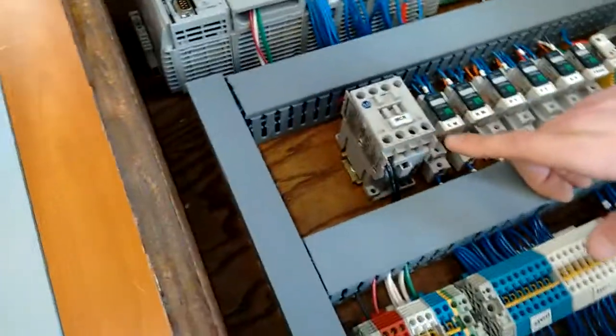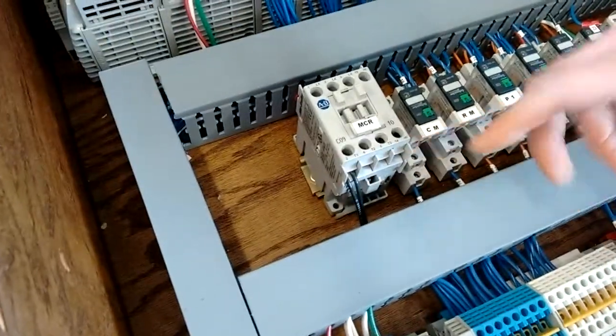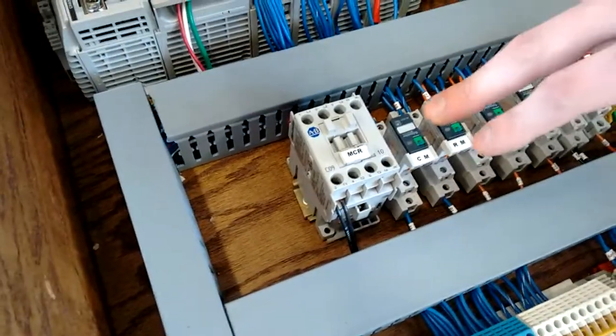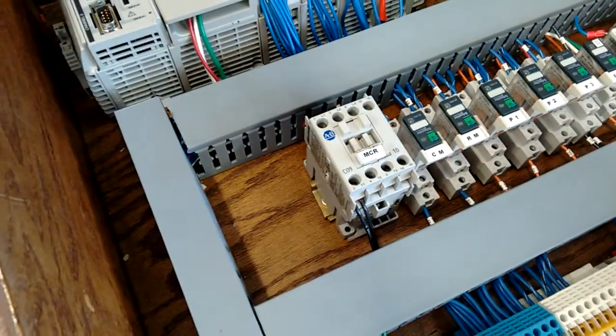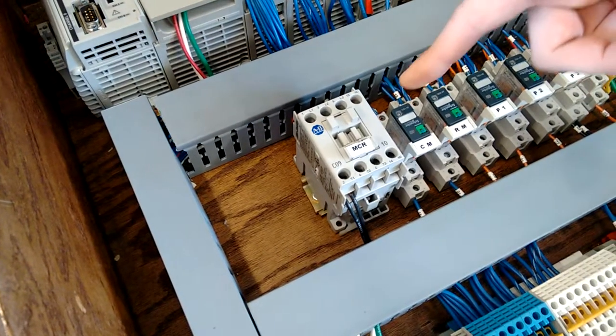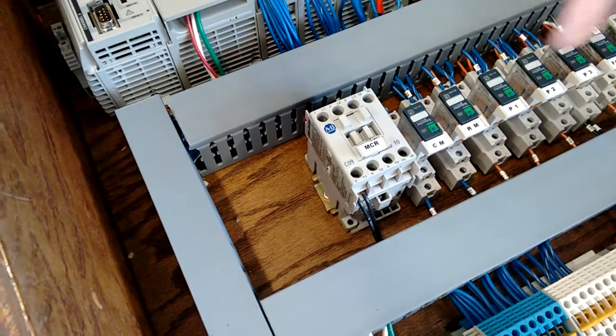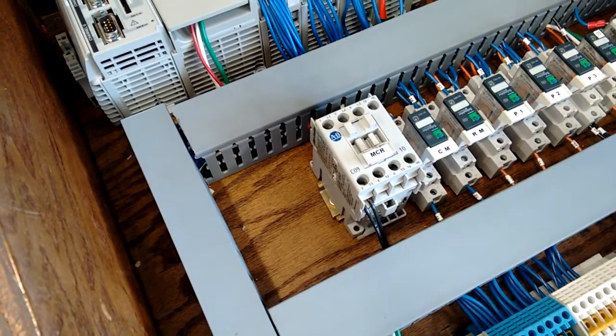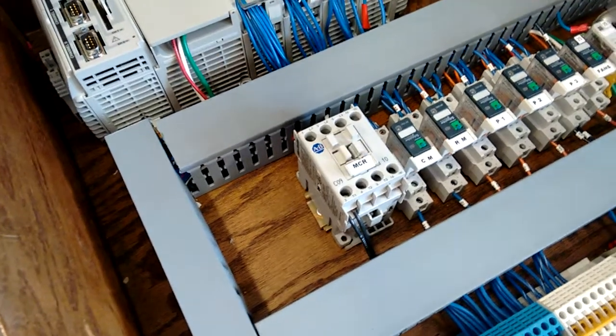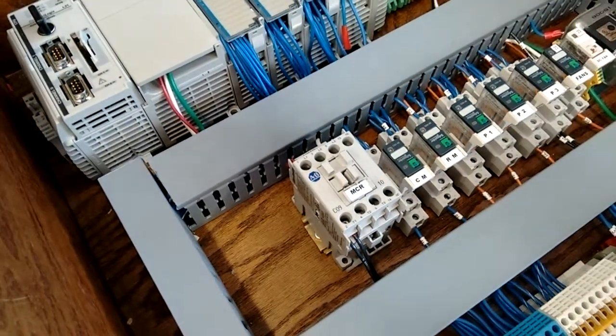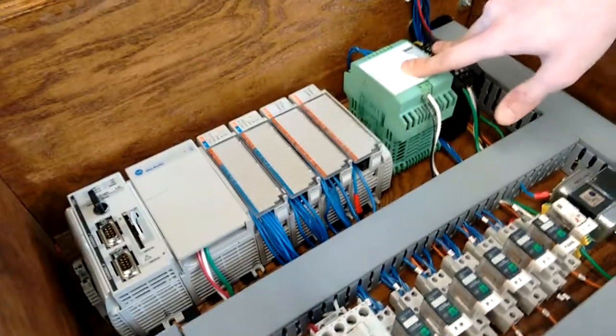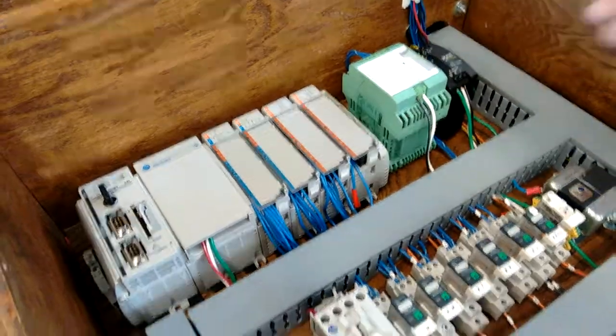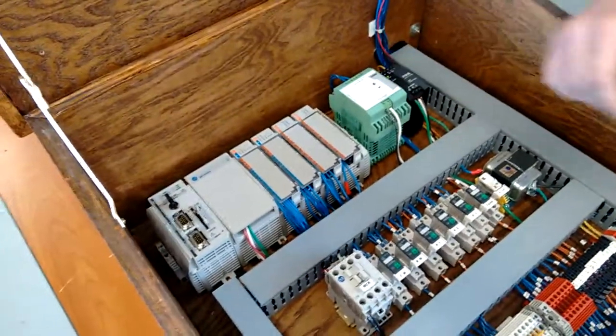Now, down here, we have our master control relay. This contactor is controlled by our stop button. Whenever the stop button is out, the coil is energized like it is right now. Whenever the stop button is pushed, the coil de-energizes, which kills power to our two power supplies. So, no field devices can be energized when it's pushed.